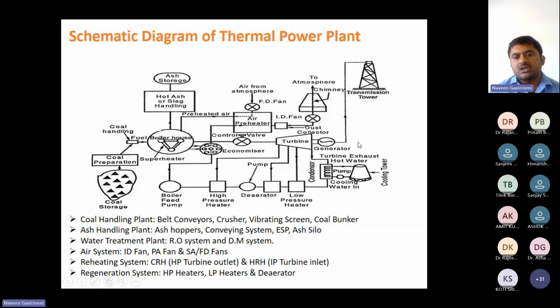And SOx, NOx comes under, earlier NOx is 600 milligram per normal cubic meter. Now it will come down to 300. Both SOx and NOx only 300. So this is the ash handling plant. Coming to the next one, water treatment. The water treatment is the most important part, on which boiler life depends. If water treatment is not there, the boiler life is going to go down because of the rust and all the things.